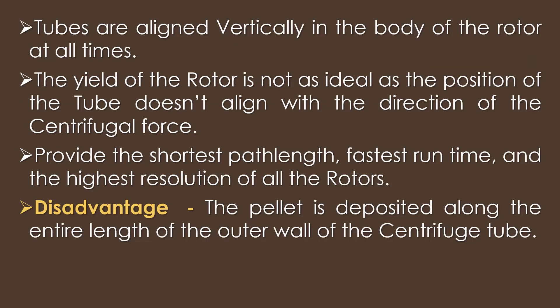In the vertical tube rotor, the tubes are aligned vertically in the body of the rotor at all times. The yield of the rotor is not as ideal, as the position of the tube does not align with the direction of the centrifugal force. Vertical rotors provide the shortest path length, fastest run time, and the highest resolution of all the rotors. The pellet is deposited along the entire length of the outer wall of the centrifuge tube, which is a major disadvantage because the pellet tends to fall back into the solution at the end of centrifugation.